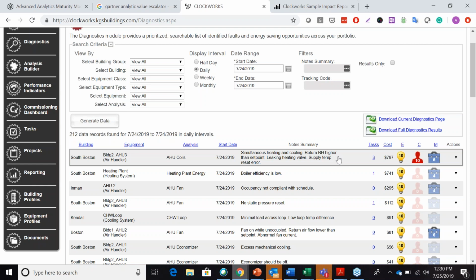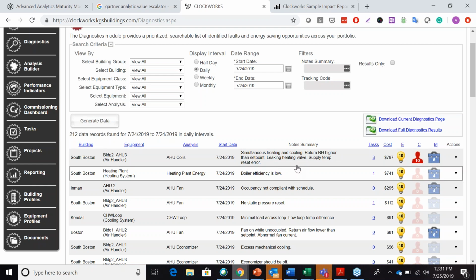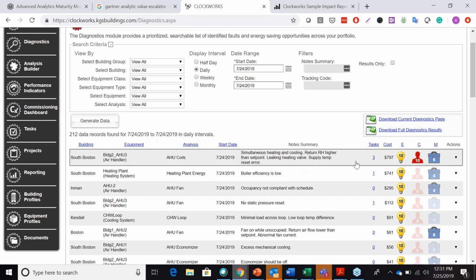We know that all it takes is one keystroke to override that sequence. And maybe it was a good reason, maybe it wasn't, but we want to bring it to attention. Now, I'll point out, as we mentioned before, that one of the qualities of next generation FDD is the ability to string multiple findings or multiple rules together to get to that root cause. So what we don't want is to have simultaneous heating cooling be one line item, to have return RH higher than set point being a second, leaking heating valve to be a third, because it means that you have really a mess of individual fault findings that become hard to prioritize.